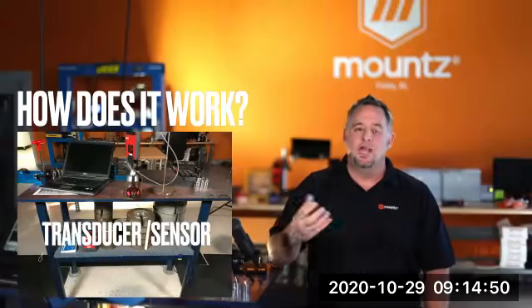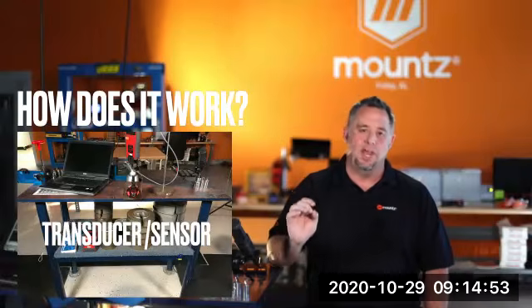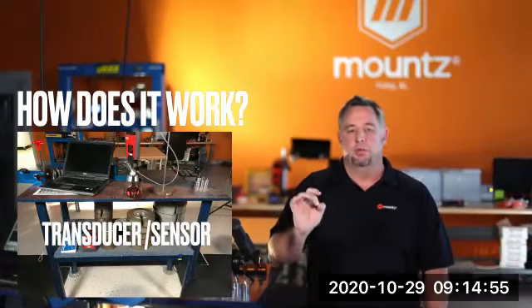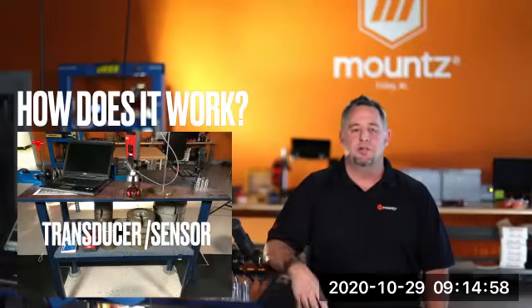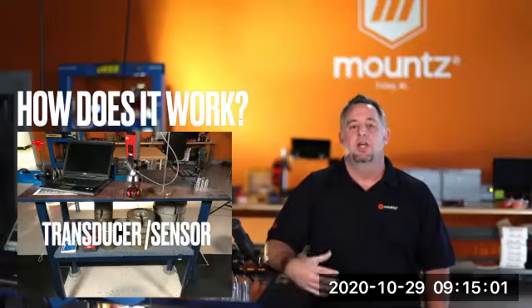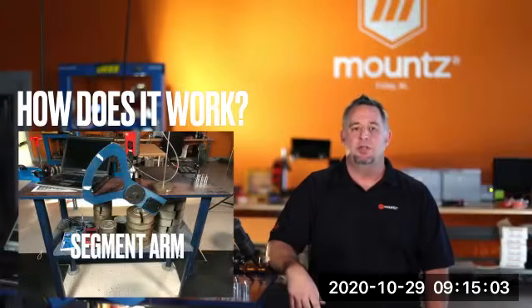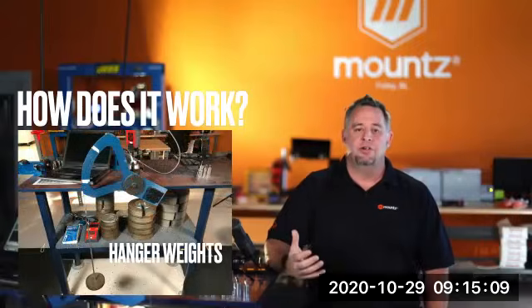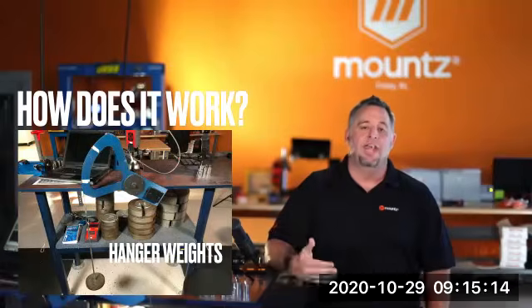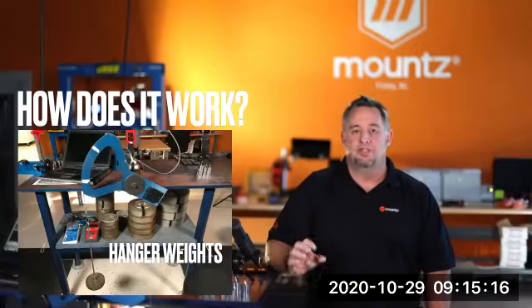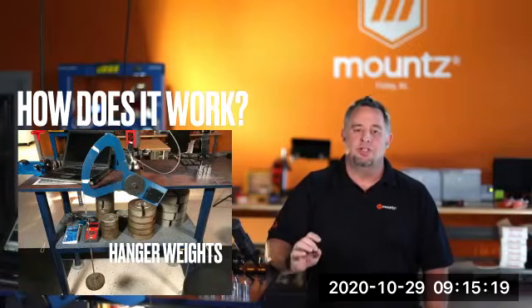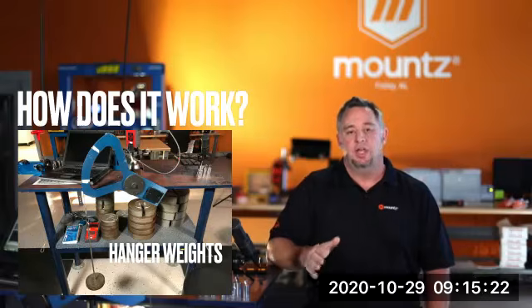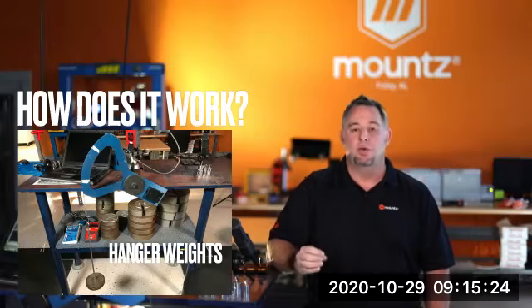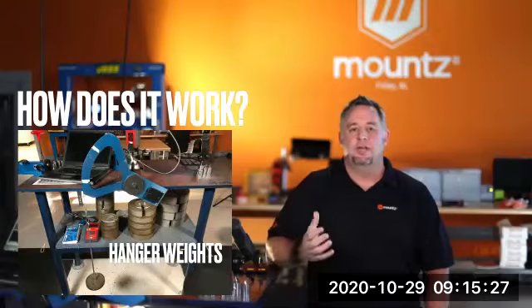And so what does that look like when we do the setup on the actual models that we're testing? So first we have our transducer, which is mounted into the bracket. And then we add a segment arm to that. And then from that segment arm, we add our different hangers and weights at the known values, or excuse me, the known weights that are needed to calibrate the particular sensor that's being used. So in most cases, we have either a call out for a 3-point calibration, or it's going to be a 5-point calibration.